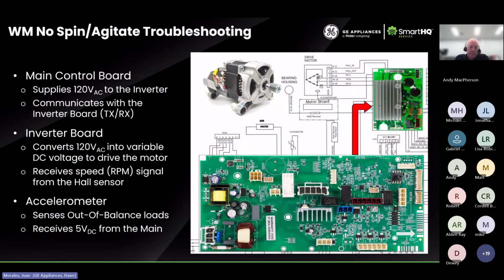Now, there's communication between the main board and the inverter. We kind of talked about that earlier before. What was it? The speed signal, the 5 volts DC, all of that. And then there's also going to be voltage that's generated at the inverter, which is DC voltage to drive the motor. Now, you could forget about measuring that because there's no way to measure it, there's no known value that you could take a multimeter and put it there, but I'm just letting you know there's DC voltage coming from the inverter to drive the motor. And at the same time, the motor, as it's spinning, is going to feed back signal, through the Hall sensor, to the inverter, which essentially is going to also go back to the main board, telling it how fast it's running. So that's your RPMs. Now, if any of these fail, guess what the symptom is going to be? No spinning action, all right?